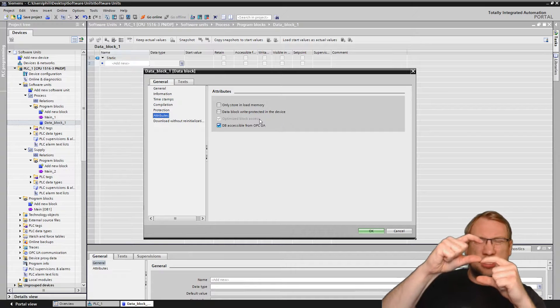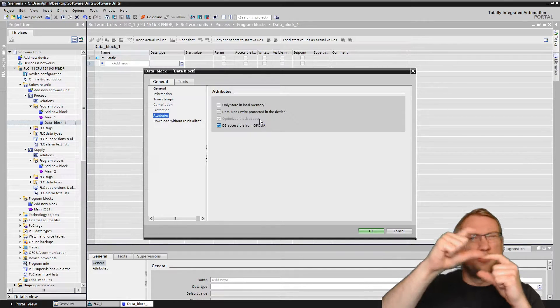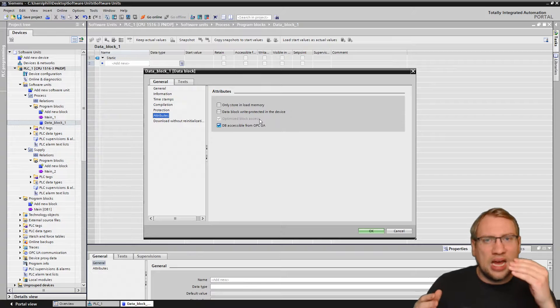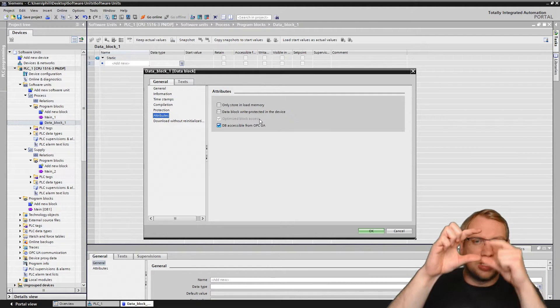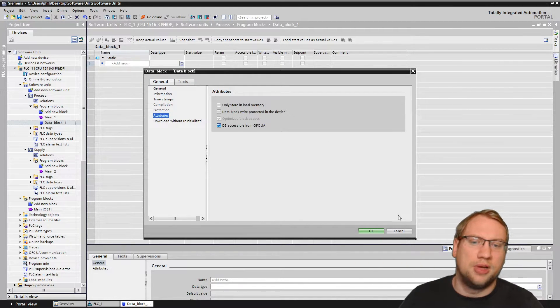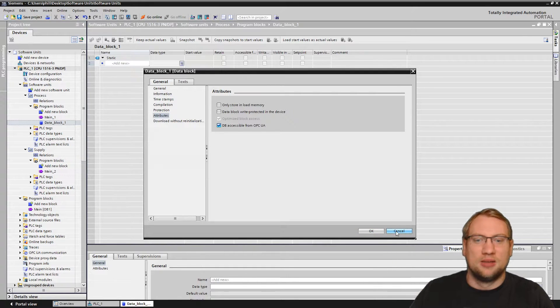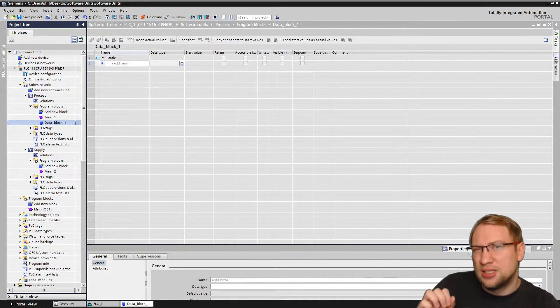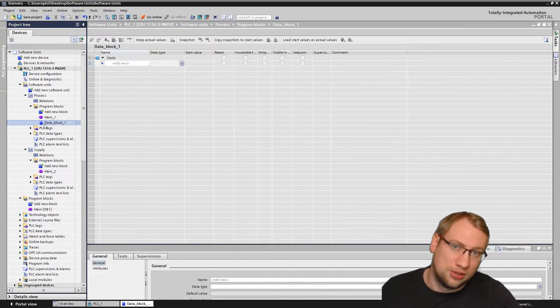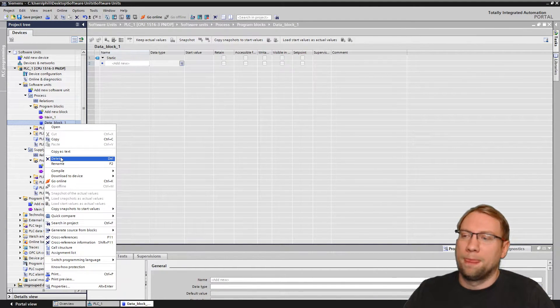It's automatically on. It's also on for all other blocks you create outside a software unit, but there you can turn it off to work address-based. Inside a software unit, you cannot work address-based anymore — it is symbol-based, tag-based, and it has to be. If it were otherwise, the units couldn't work independently, because working with addresses would cause conflicts. If a new tag is created, addresses shift and they overlap — that won't work. Using tags keeps it totally flexible. Our blocks are all optimized, which is basically an advantage, but be aware that some things outside the PLC do not work with optimized access.